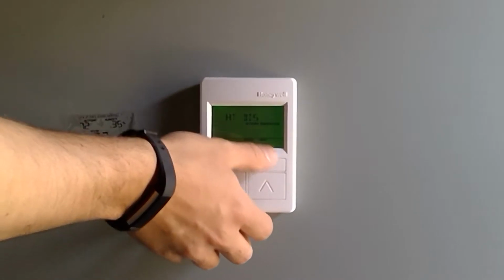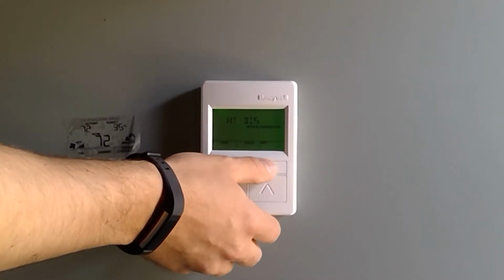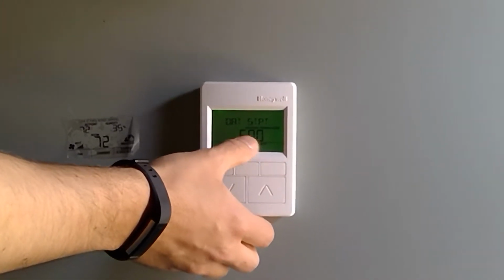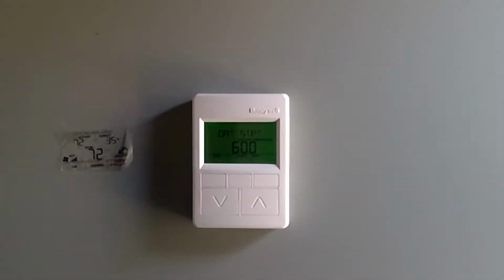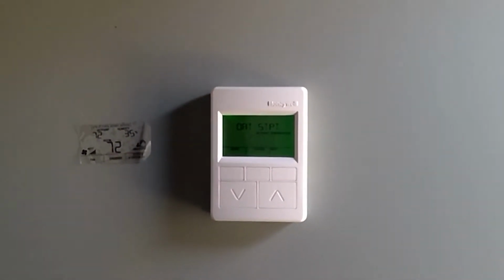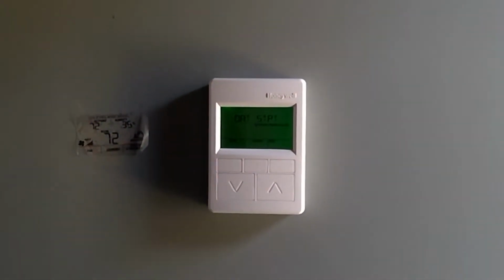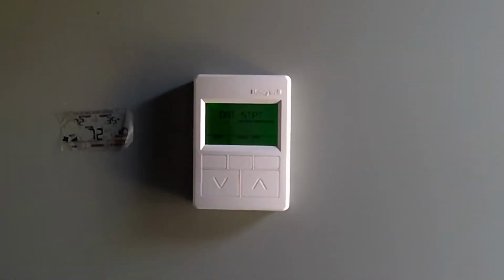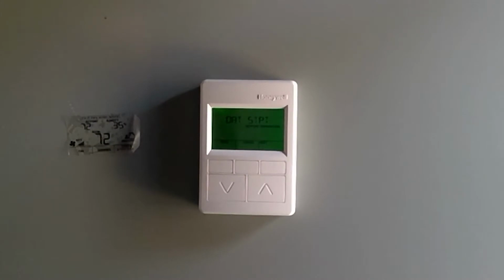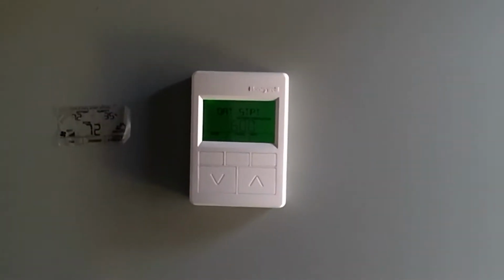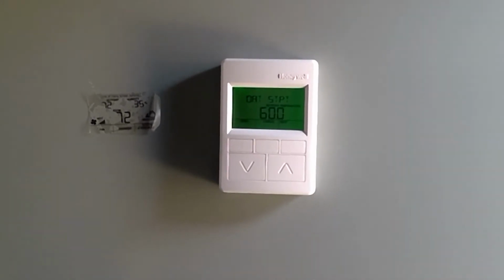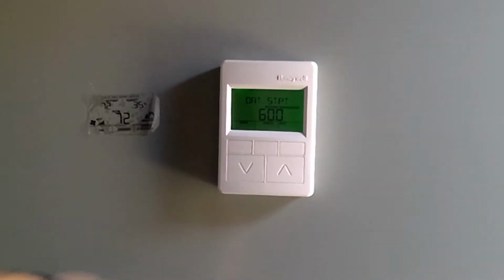But for right now, we're just going to continue scrolling through, and it's just going to save this value anyway. So heating discharge, outdoor air set point 60. So 60 degrees, and it goes up 2.5 degrees for cooling, down 2.5 degrees for heating. So when my outside air temperature is 60 degrees, I have no heating or cooling. There's a dead band up and down. When outside air goes to 62 degrees, I'm in cooling mode. When I go to 58 degrees, it's in heating mode. In between, it's ventilation only.